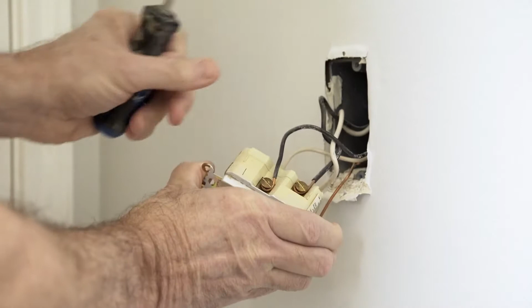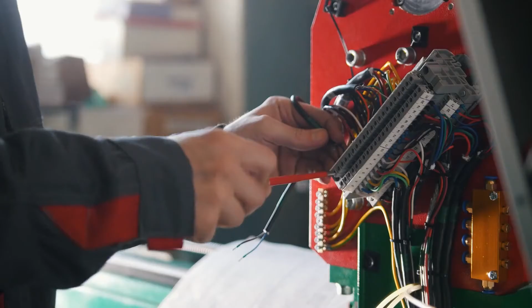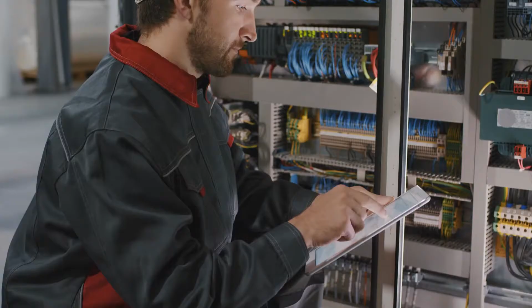They're also commonly experienced during windy days, where the problem can be caused by frayed wiring in the weatherhead, causing a short when the cables move. A weatherhead is the outdoor fitting where overhead cables from the power line come into the house, and if this is the cause, the danger level is pretty high, since the frayed wiring can arc and start a fire.